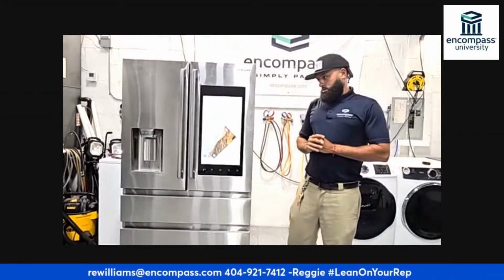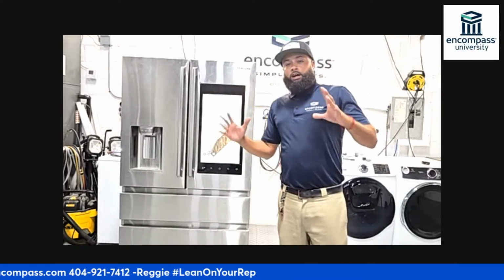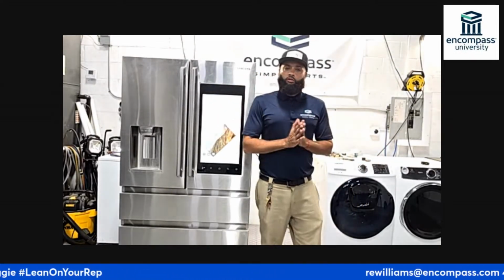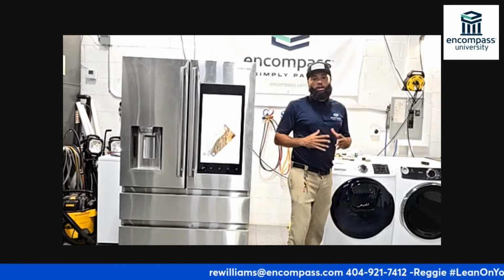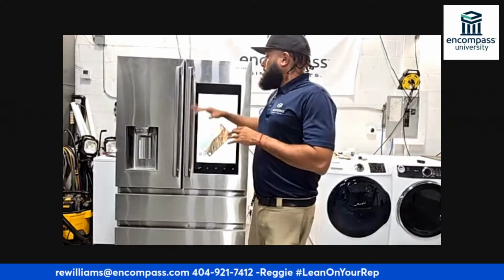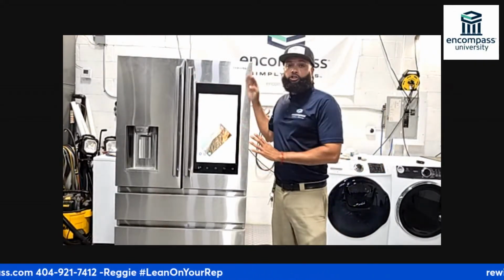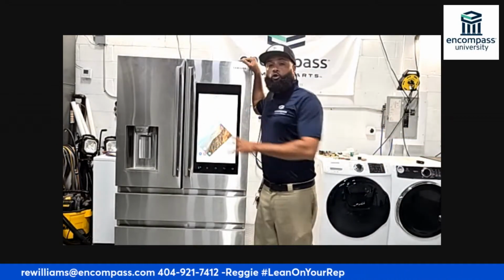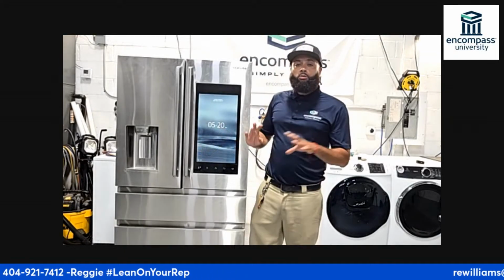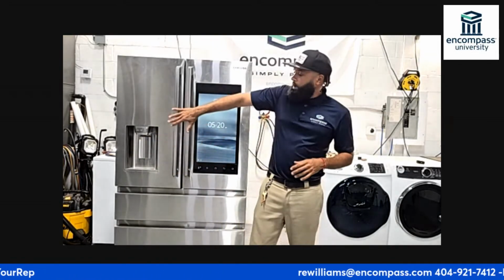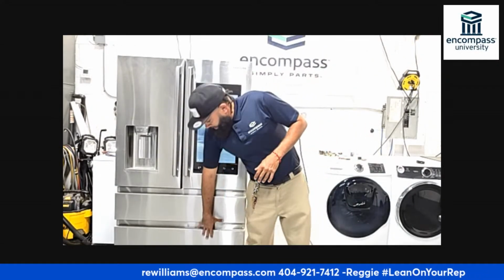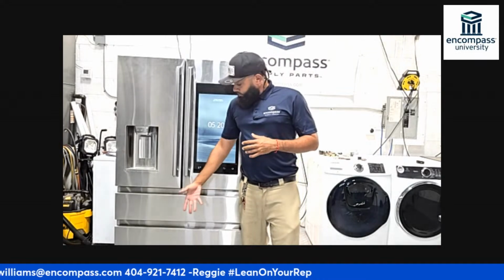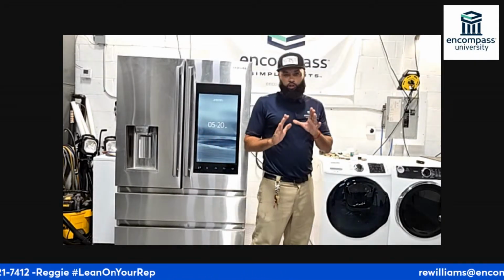Let's speak about it. When it comes to refrigerators in general, a couple things we need to consider. Number one, what the temperatures need to be. We can't know something's broken if it's not operating the way it's intended. So how is it intended? Fresh food compartment, always 37 degrees plus or minus 3 — that's our objective up top. Down below in the freezer compartment, we want 0 plus or minus 3.